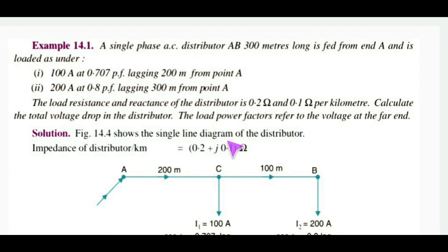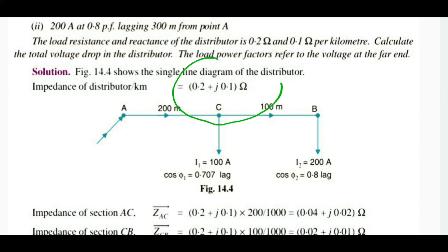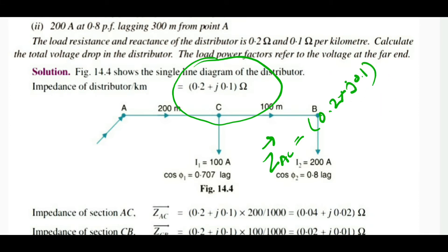Calculate the voltage drop in the distributor. Load power factors refer to the voltage at the far end. First, find the impedance of the distributor per kilometer: impedance per km = 0.2 + j0.1. For section AC (200 meters): impedance = (0.2 + j0.1) × 200 divided by 1000.